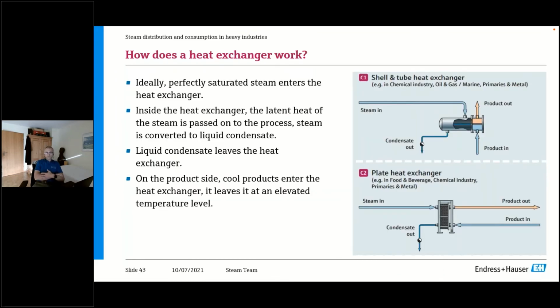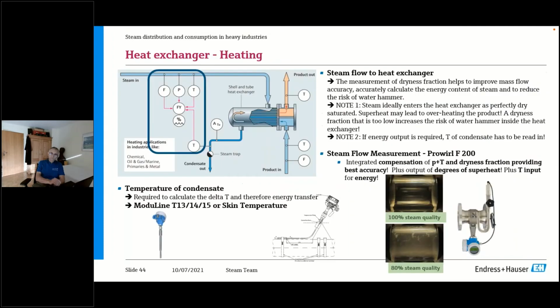Inside the heat exchanger, the latent heat of the steam is passed on to the process. So the HFG is passed on and you have condensate coming out. So HF is leaving the heat exchanger. And on the product side, you have a cool product that is entering the heat exchanger and it leaves it at a higher temperature. So the measurement here is pretty evident.